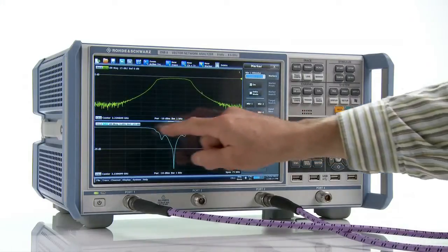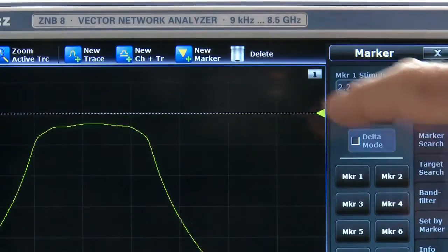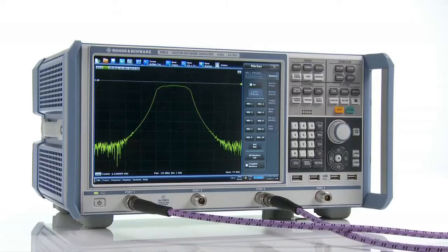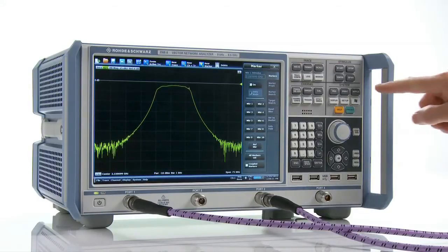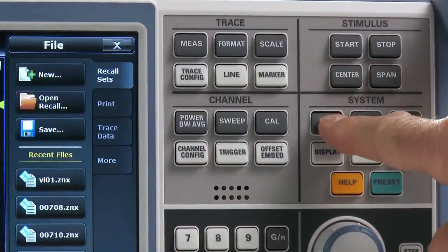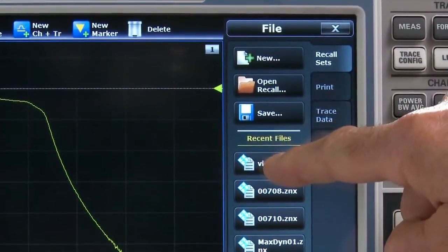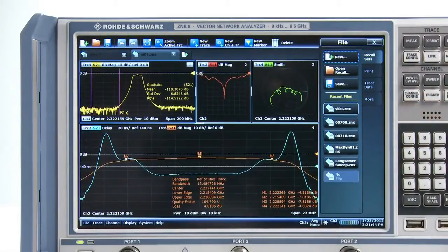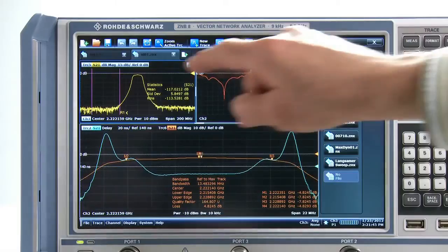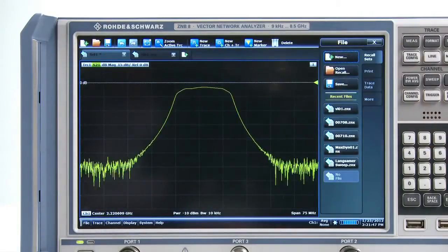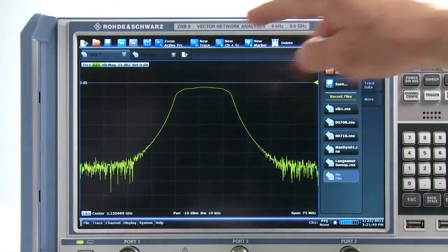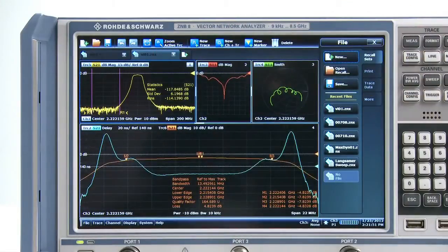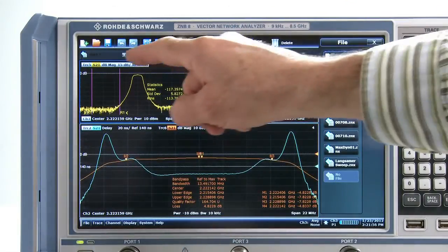When you no longer need a trace, just drag it into the trash can. Users who frequently switch between different types of DUTs will appreciate another feature of the ZNB. It lets you keep multiple complete instrument setups accessible at the same time. If you change the DUT, for example, when spot testing different filters, just tap on the setup you need.